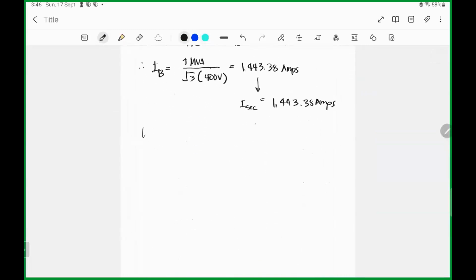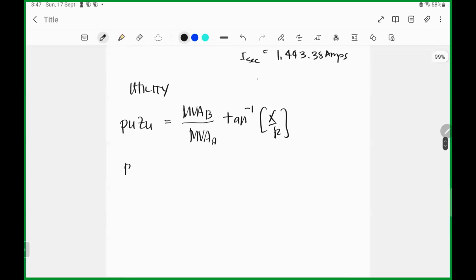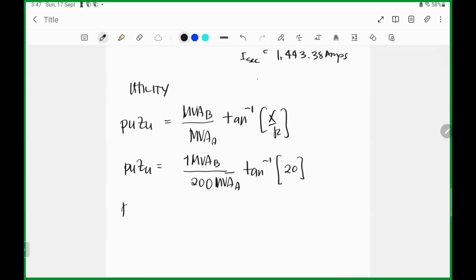So utility. Sa utility, the impedance of the utility in per unit is simply MVA base over the MVA actual. So you need to include the short circuit power factor or the reactance to the resistance ratio. So you will get the inverse tangent function of X over R. Okay. So the per unit impedance of the utility is 1 MVA, which is my base. The actual is 200 MVA. So the X over R is 20.